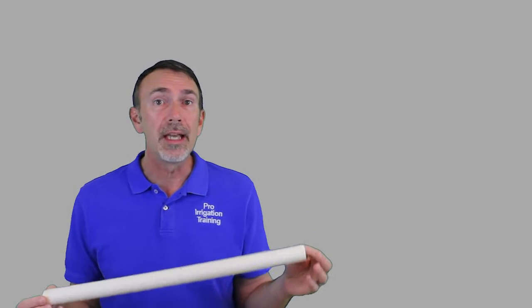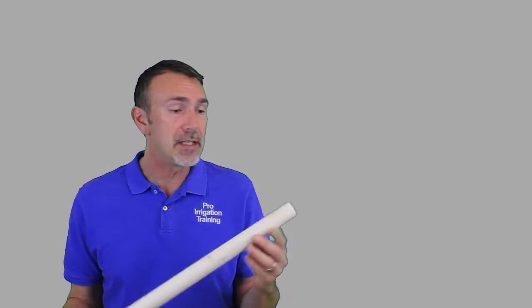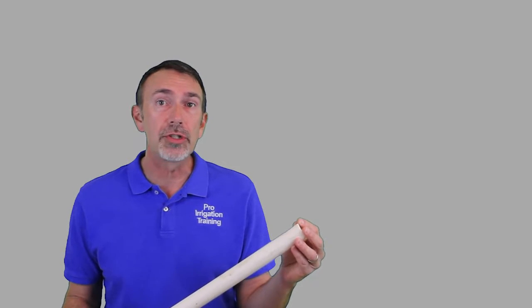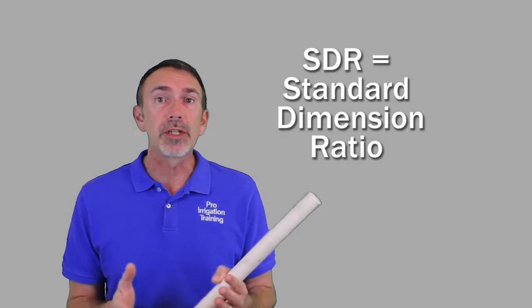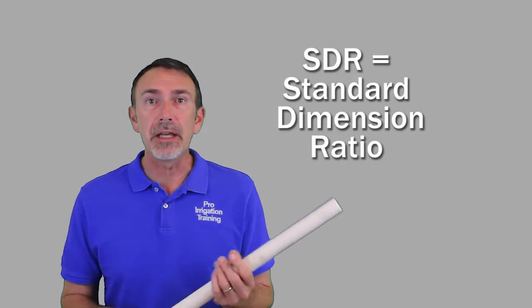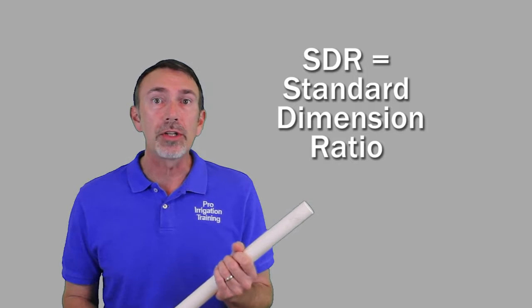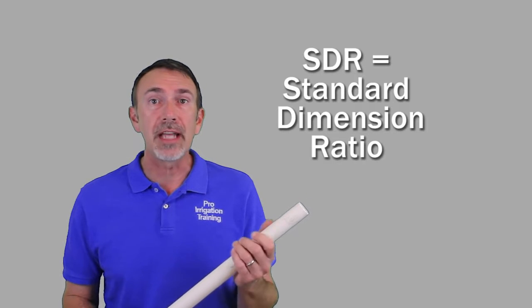What I'm holding is a thin wall irrigation pipe, this is class 200. The class 200 refers to the pressure rating of this, it has a maximum operating pressure of 200 psi. A lot of these pipes will have what's called an SDR rating. SDR stands for standard dimension ratio, and that means no matter what size of pipe that you get that's class rated—we have class 160, class 200, class 315—all of these will have the very same maximum operating pressure no matter what size pipe you use.